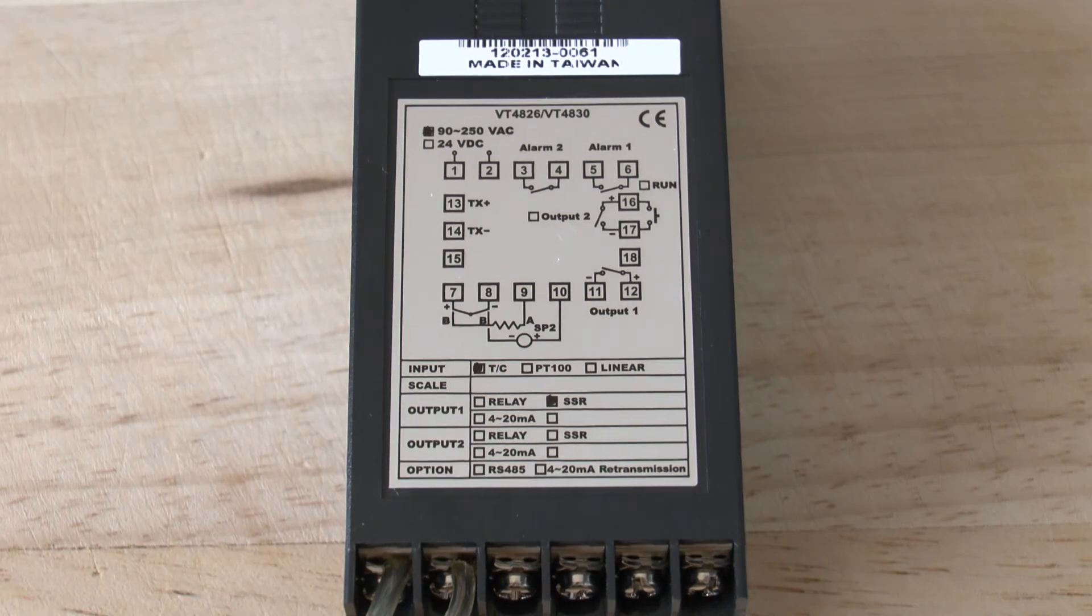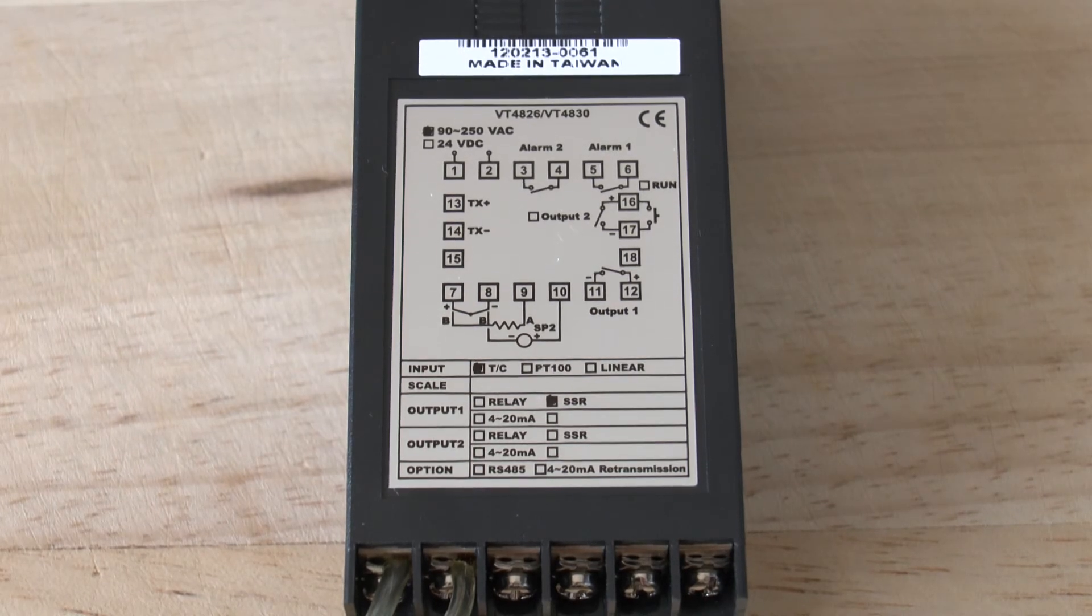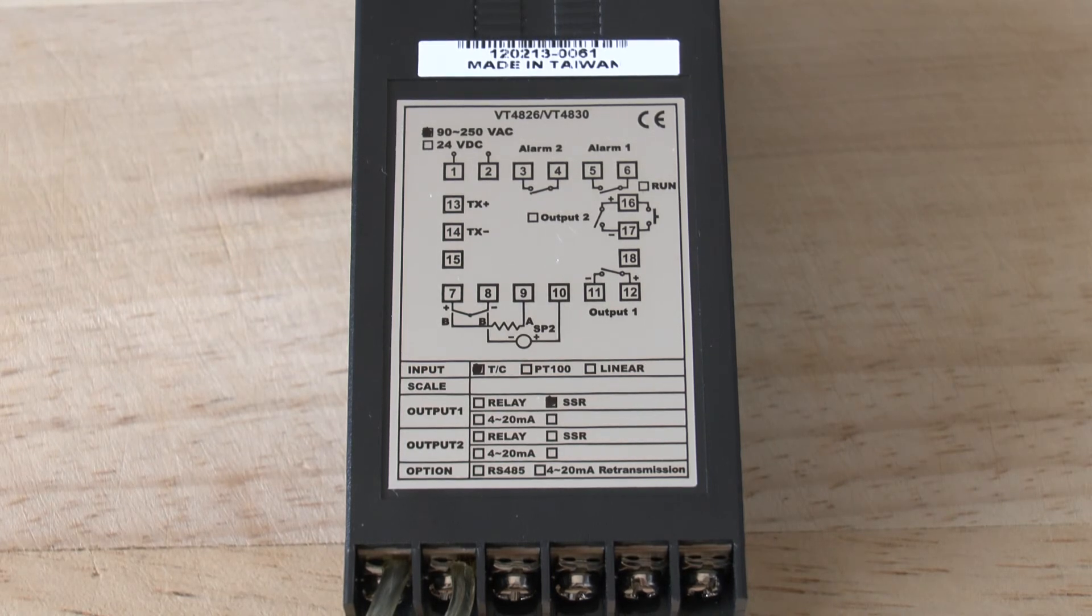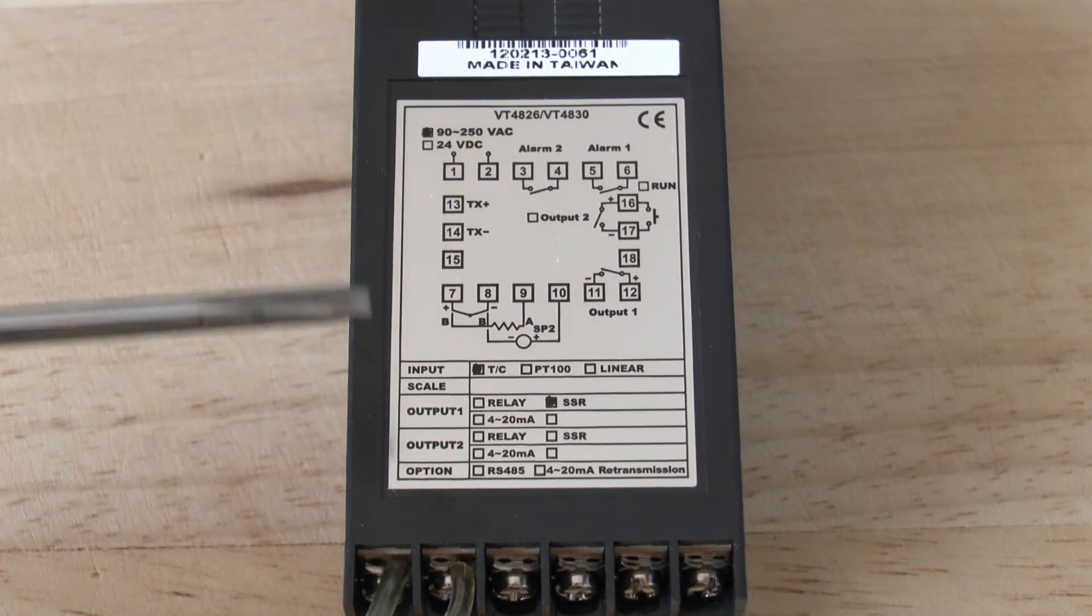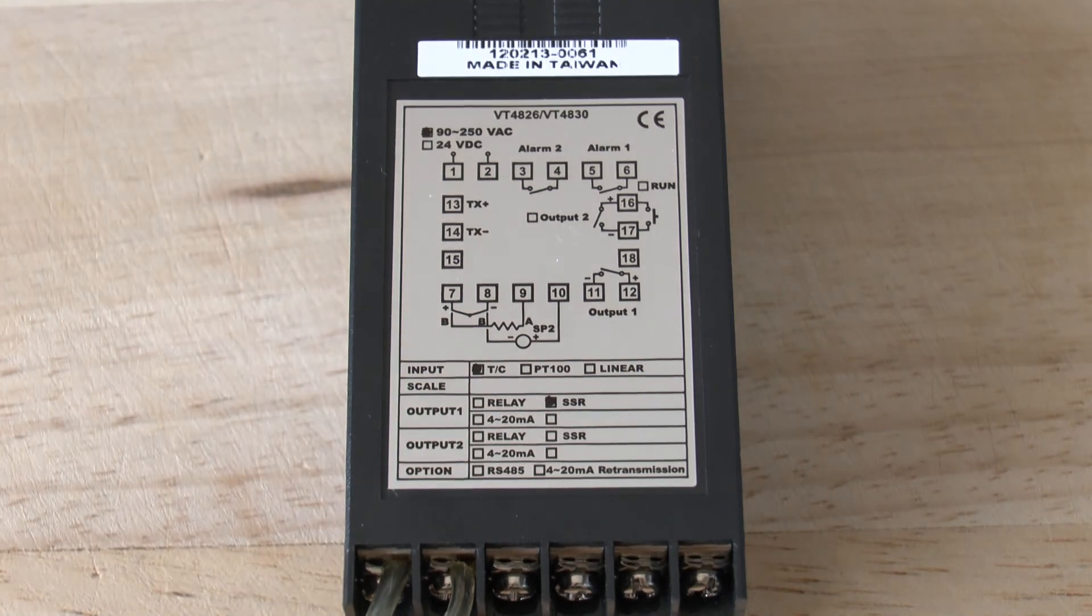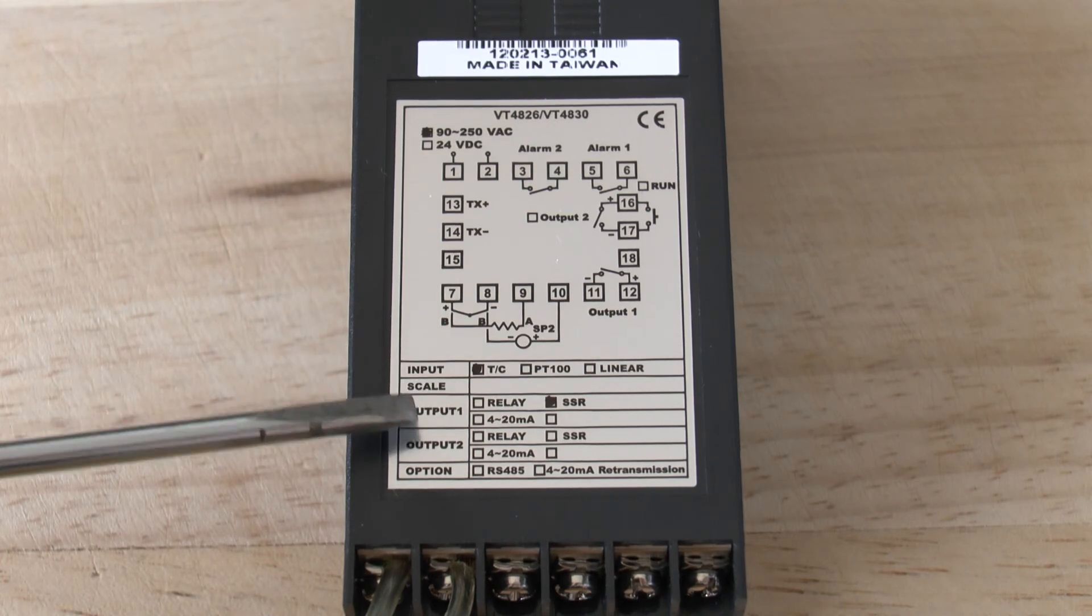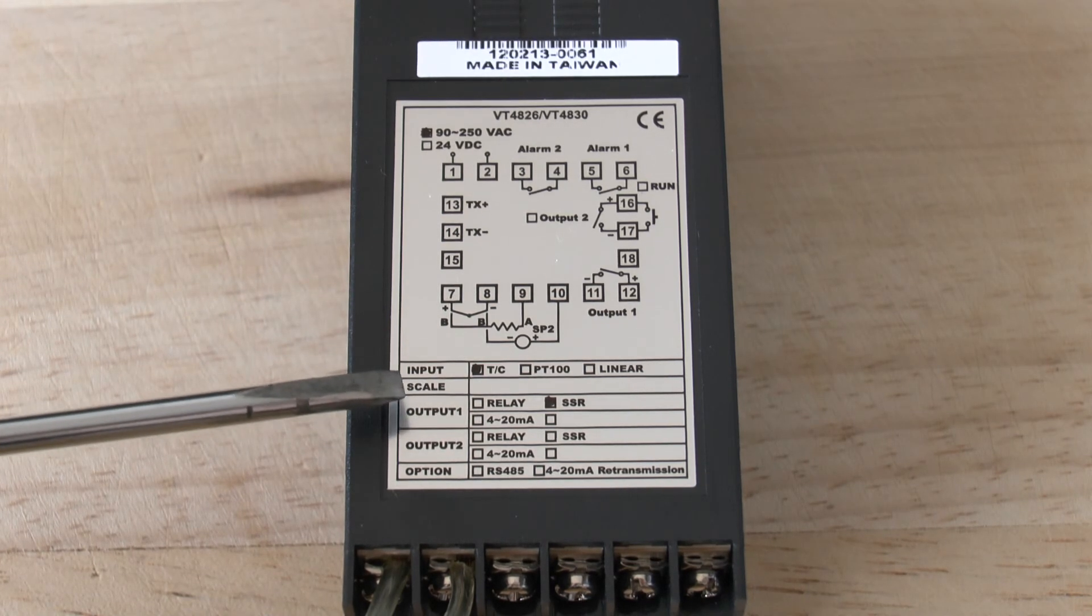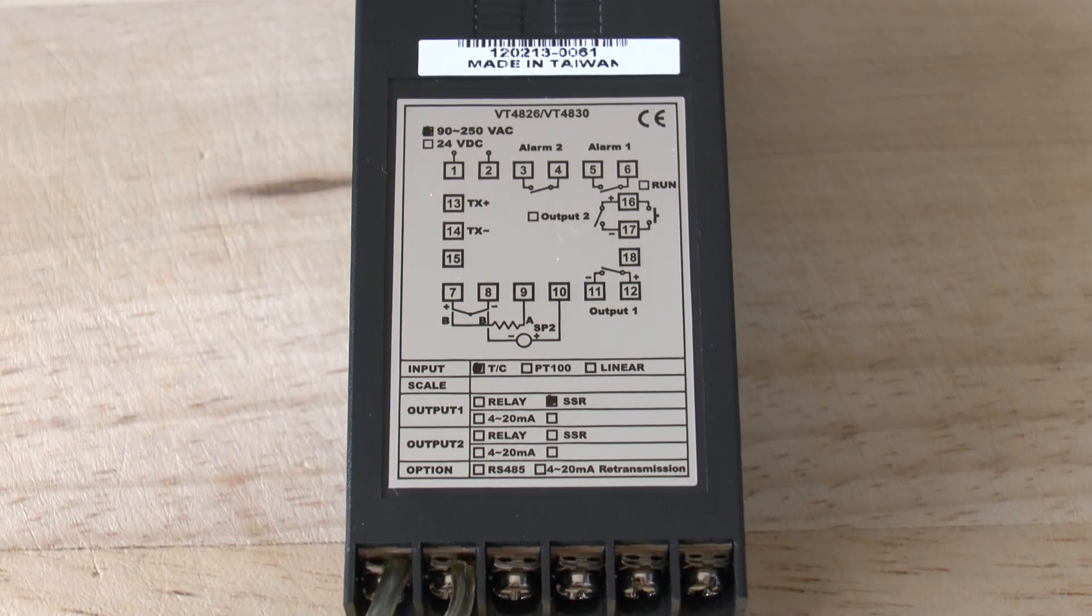So, when you first take the controller out of its box and are about to install it in your panel, please be sure to look at the label on the side, as we have just shown you. Also, check the little dots which have been filled in, indicating which options apply on your controller. As you will see, this one is a thermocouple input and for output 1, it's a solid-state relay and there is no output 2 on this particular unit.